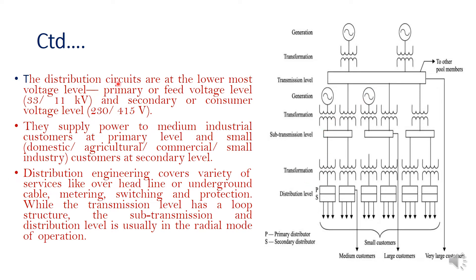The distribution circuits are the lowermost voltage level. Primary or feeder voltage level is 33 to 11 kV — that is the primary distribution. Secondary distribution level voltage is 230 or 415 volts: 230 V is the single-phase supply and 415 V is the three-phase supply. They supply power to medium industrial consumers or small domestic, agricultural, commercial, or small industry consumers at the secondary level. Distribution engineering covers a variety of services like overhead line, underground cable, metering, switching, and protection. While the transmission level has a loop structure, the sub-transmission and distribution level is usually in the radial mode of operation.